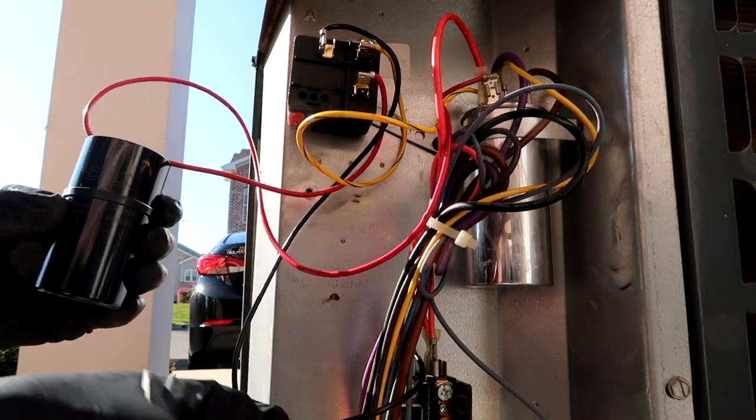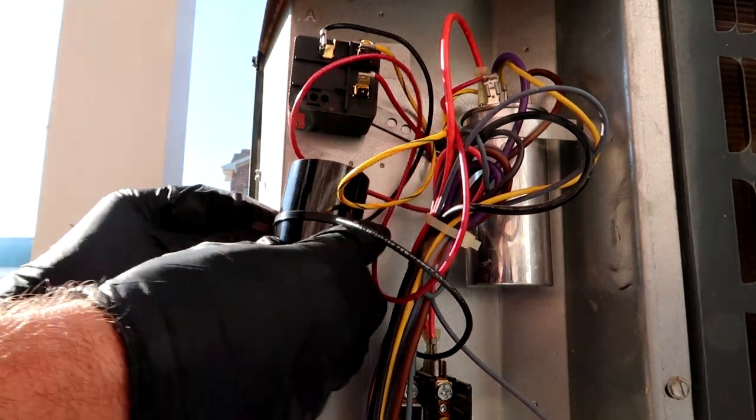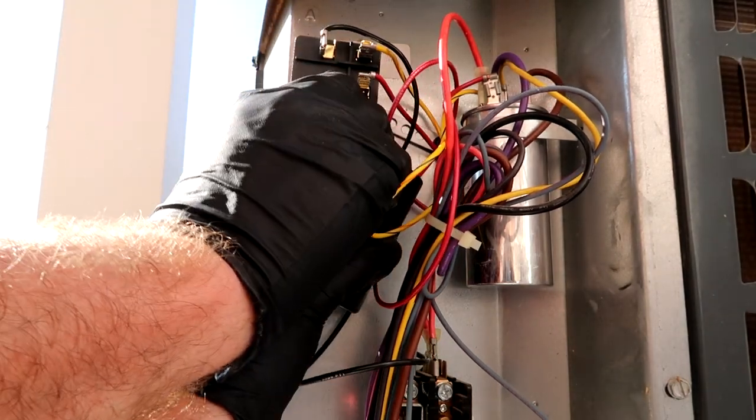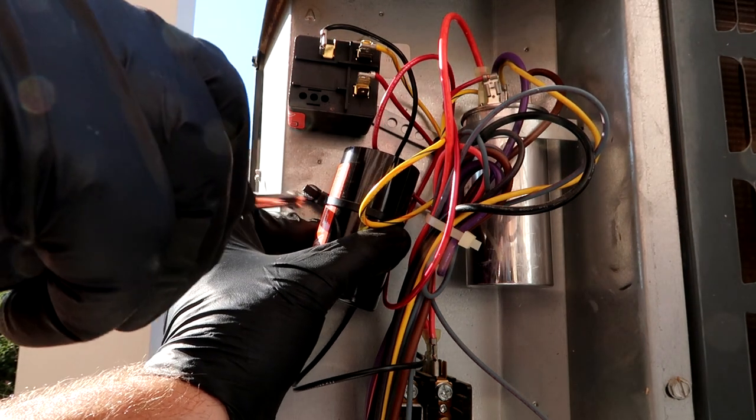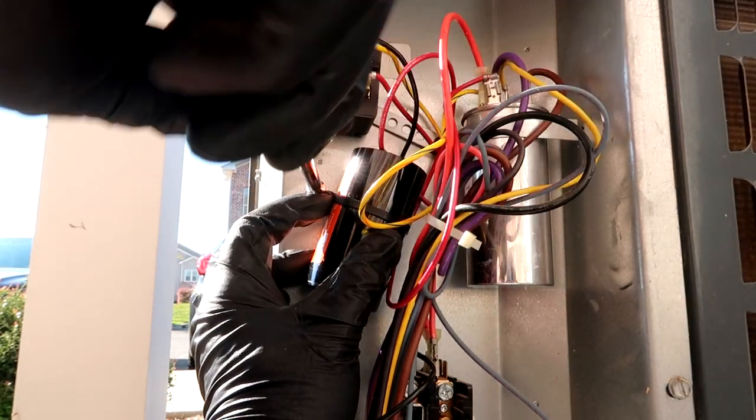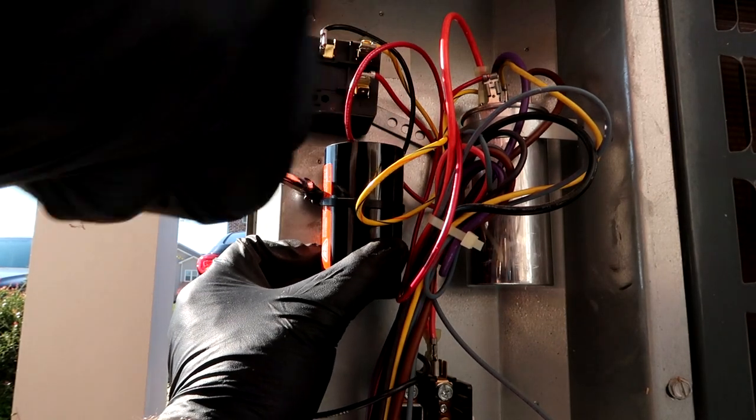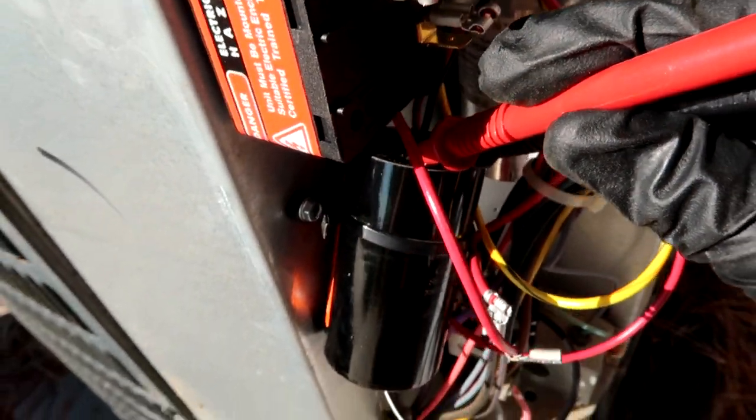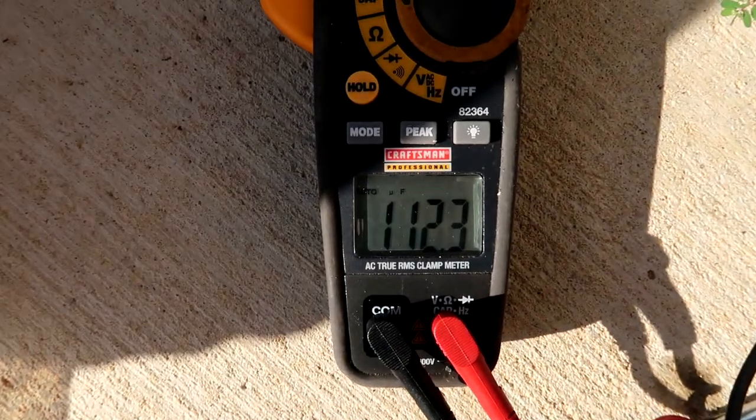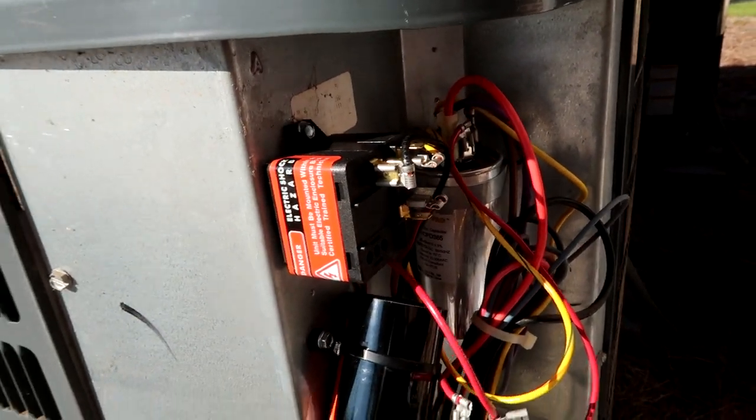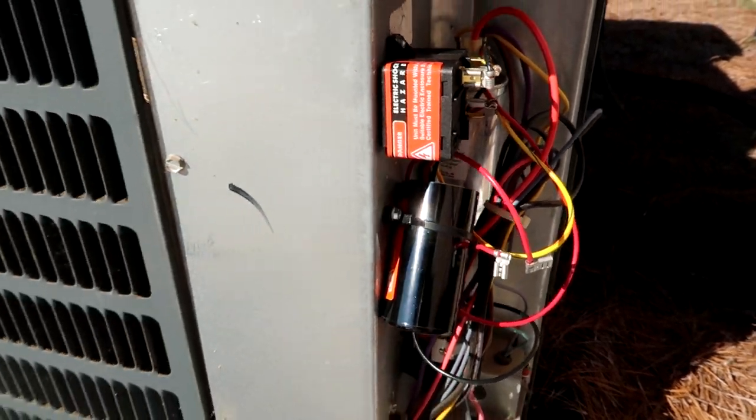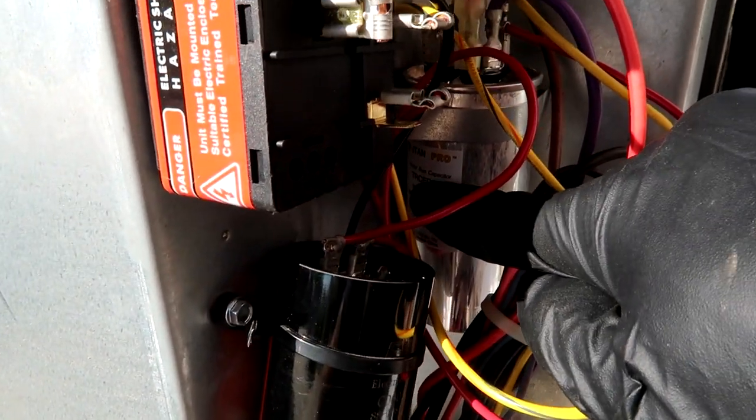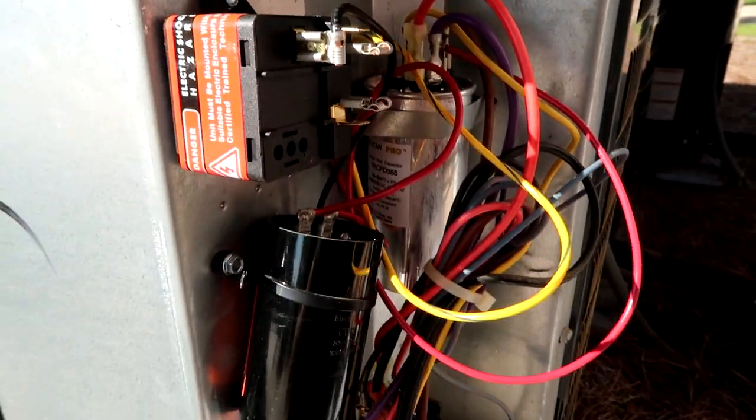That is it. Screw the hard start back down. I kind of like plumbing strap better than the zip tie they send it with. All right, this is the good hard start. Got my leads on both the terminals, and as you can see, 112. So that means it's good. Remember the other one was zero. I'm going to test the capacitor to make sure that's good. The capacitor is a 35/5. I got 35 on the herm and 5 on the fan, so it's good. Let's go turn the breaker back on and see what happens.